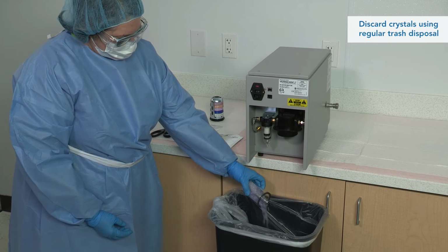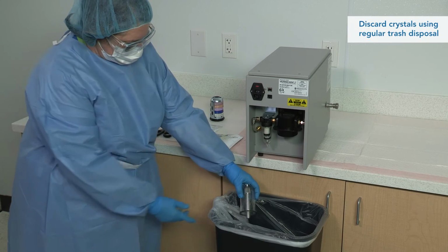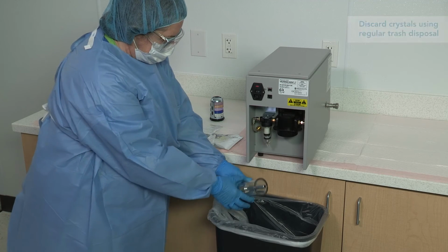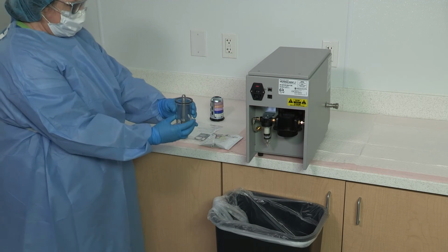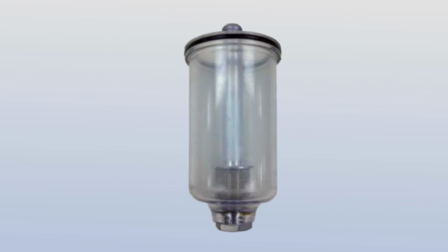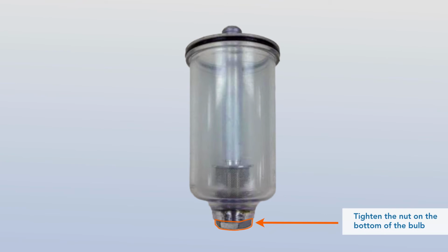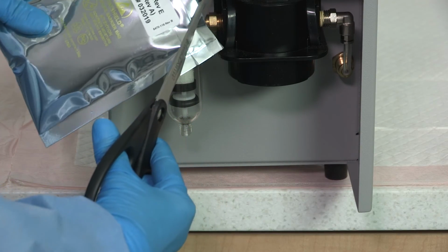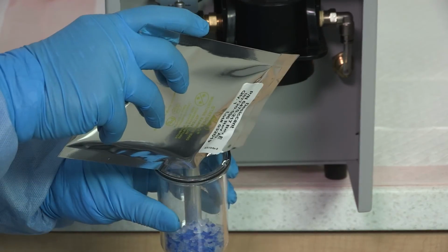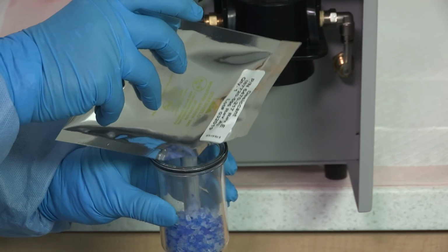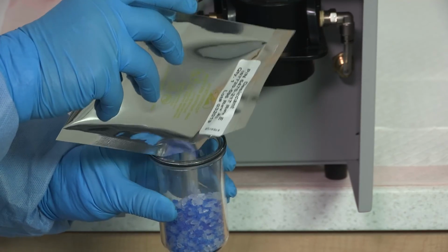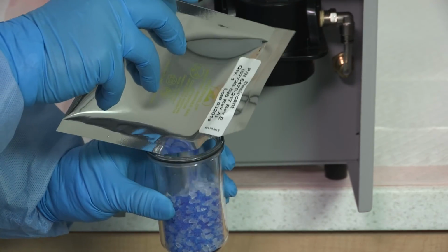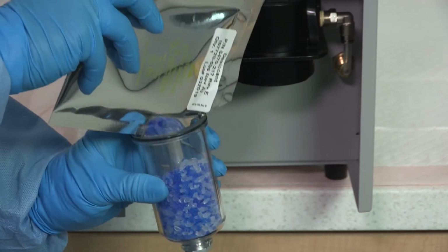Empty and discard any used drying crystals from the bulb using regular trash disposal. Check the bulb for leftover crystals clinging to the inside. With your fingers, tighten the nut on the bottom of the bulb. If this nut comes loose, it can cause a leak test to fail. Cut a corner of the bag to create a small hole and carefully pour the entire bag of new crystals into the glass bulb. Do not allow crystals to enter the metal tube located in the center of the bulb.